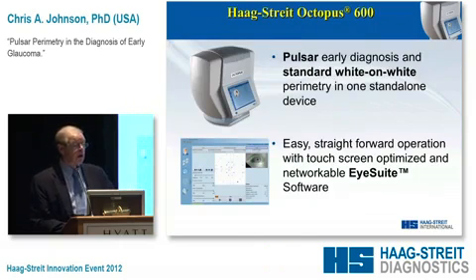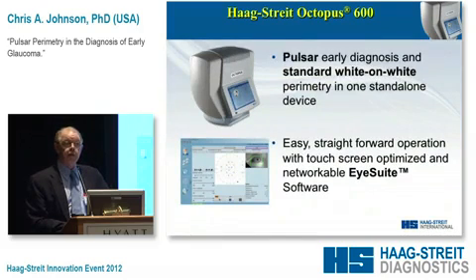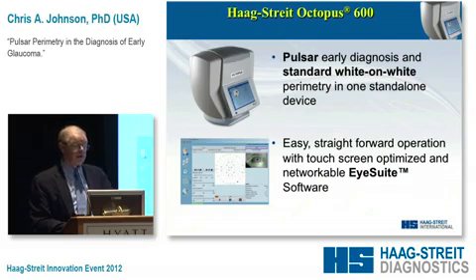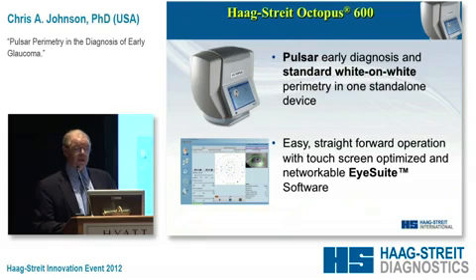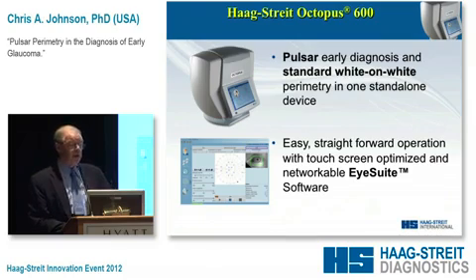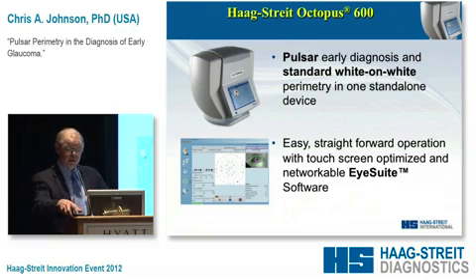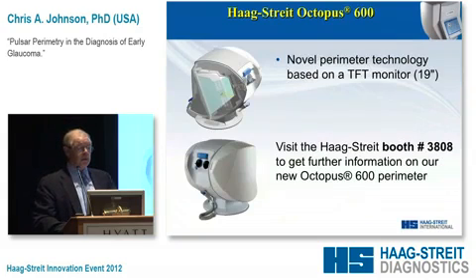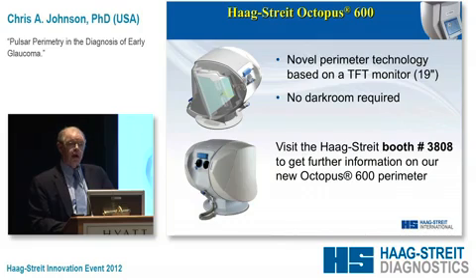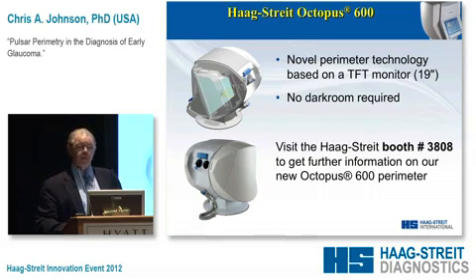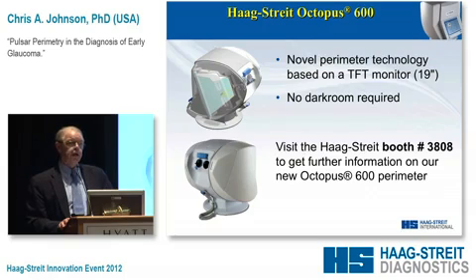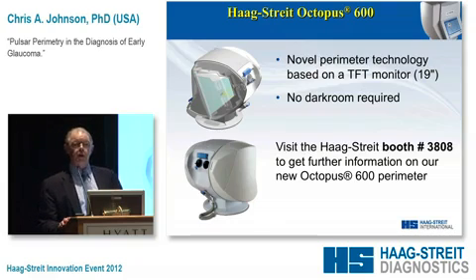This is the Pulsar Perimeter, and as you can see, it is quite compact in size with very nice operation. We have one of the Octopus 600s with Pulsar Perimetry that we are currently doing evaluations with. It has a very unique design and uses tendency-oriented perimetry—the TOP strategy—to perform threshold testing.